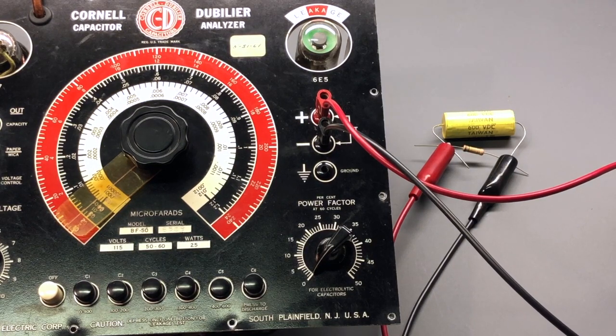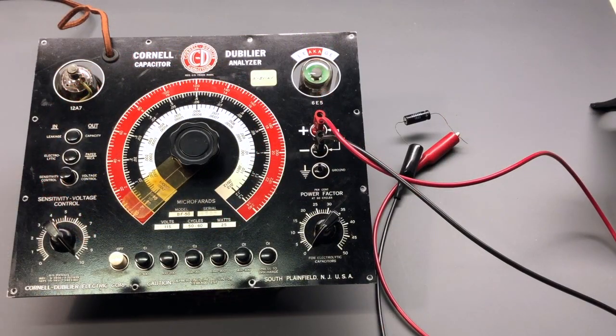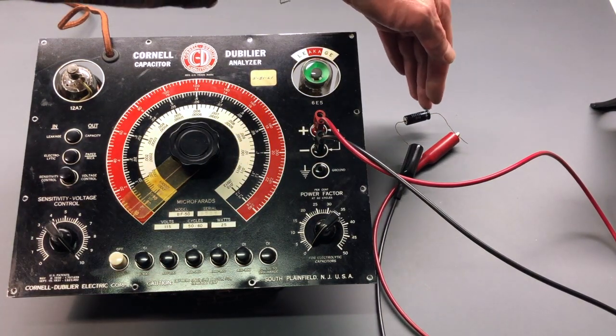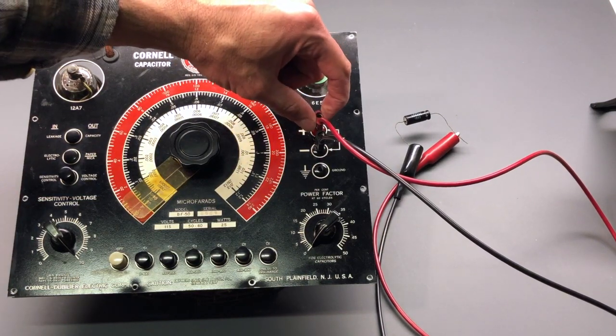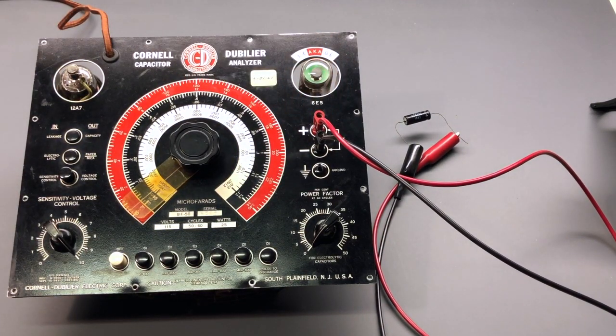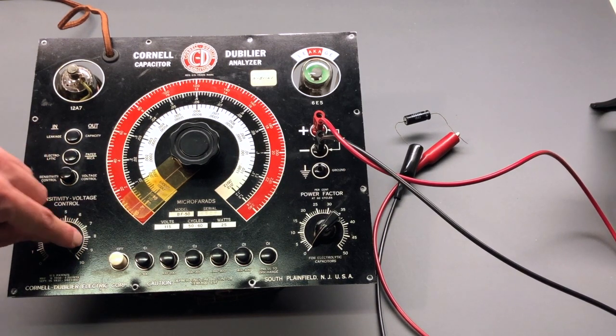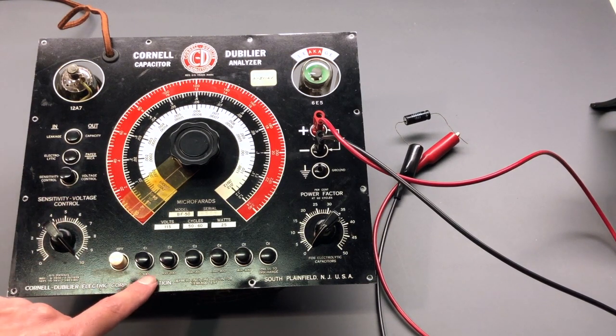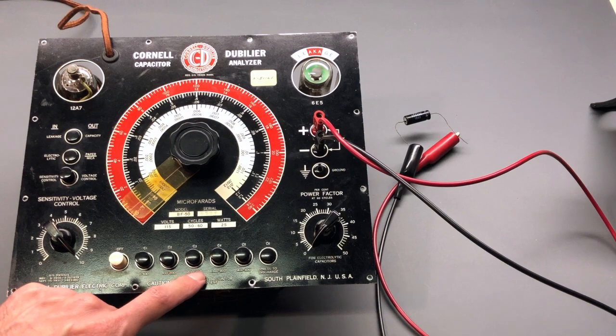So the next step is to check out an electrolytic capacitor, and we'll look at using these voltage ranges down here. So let me get the tester repositioned with an electrolytic capacitor. Okay, the tester is now connected to a 300 volt 3 microfarad electrolytic capacitor. And again, with an electrolytic capacitor, you want to watch that the positive is connected to the positive test jack over here. The polarity is very important. You can see over here it's in the leakage mode, and now we're in the electrolytic mode, and this voltage control is turned to the maximum, so that on each of these ranges it would be applying either 100, 200, 300, and so on volts.